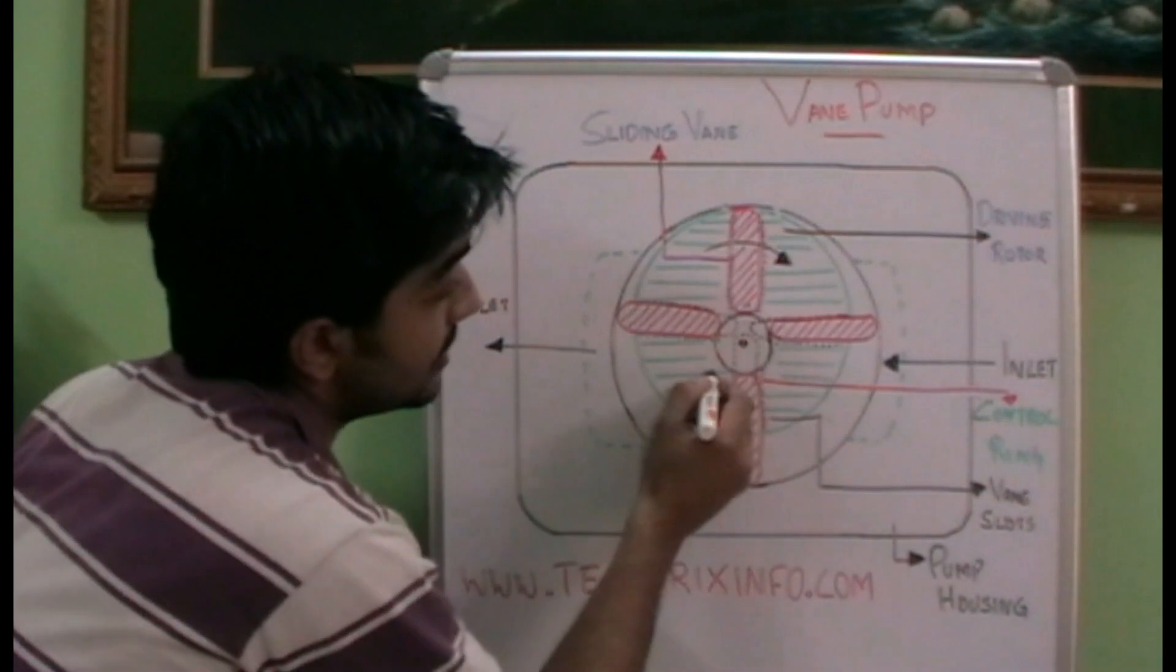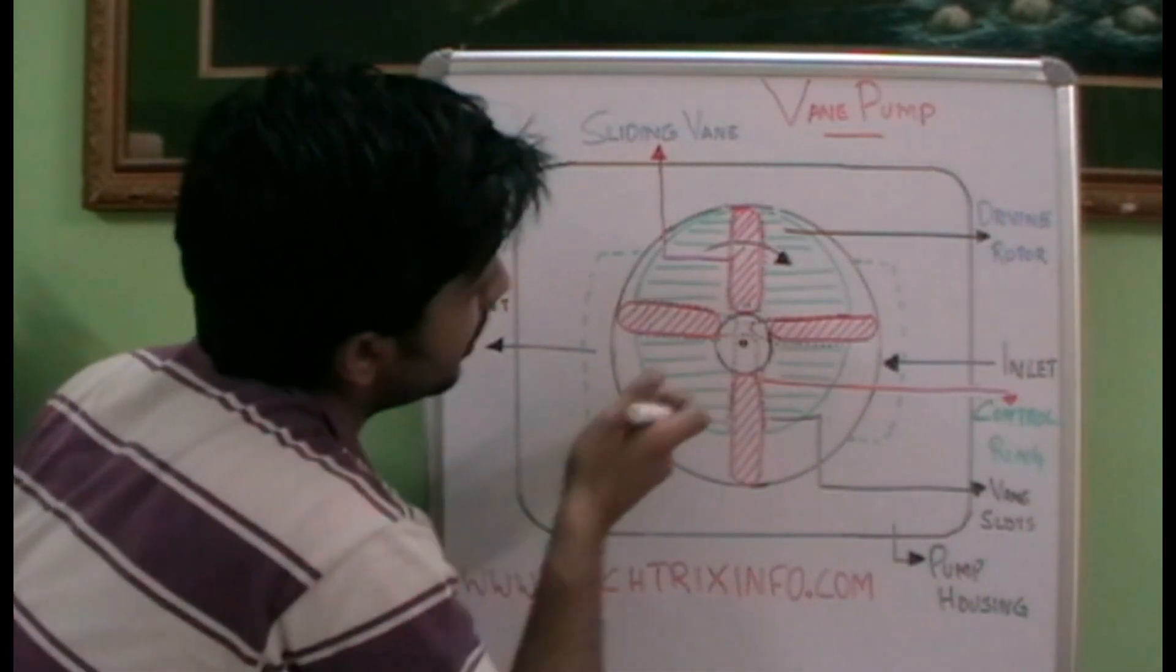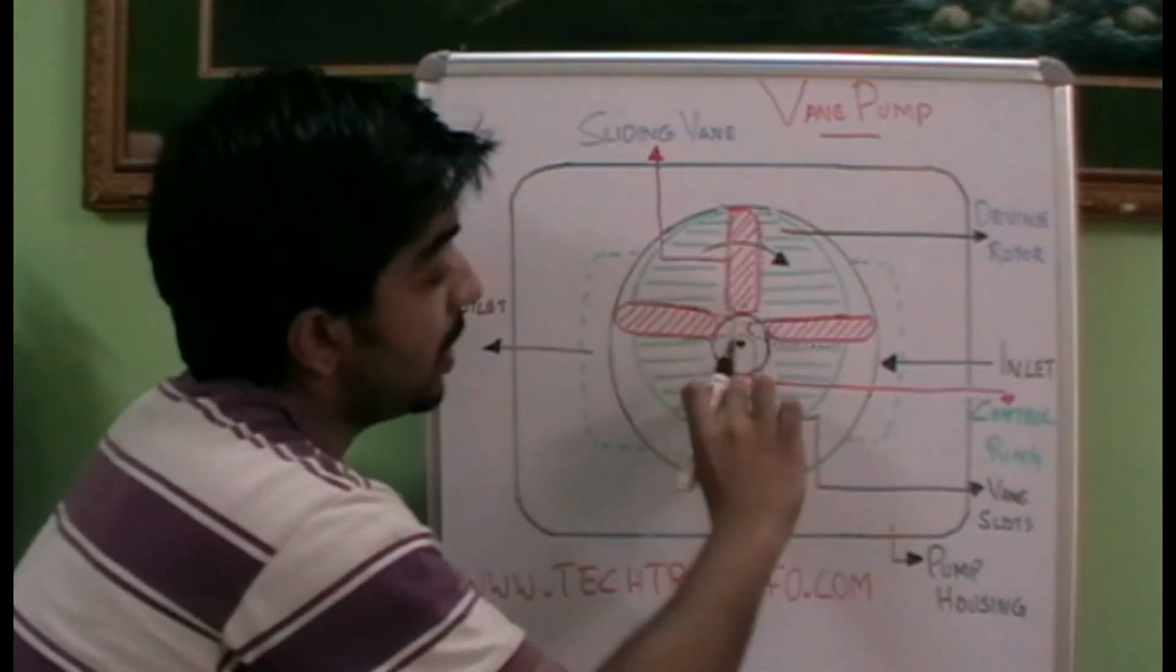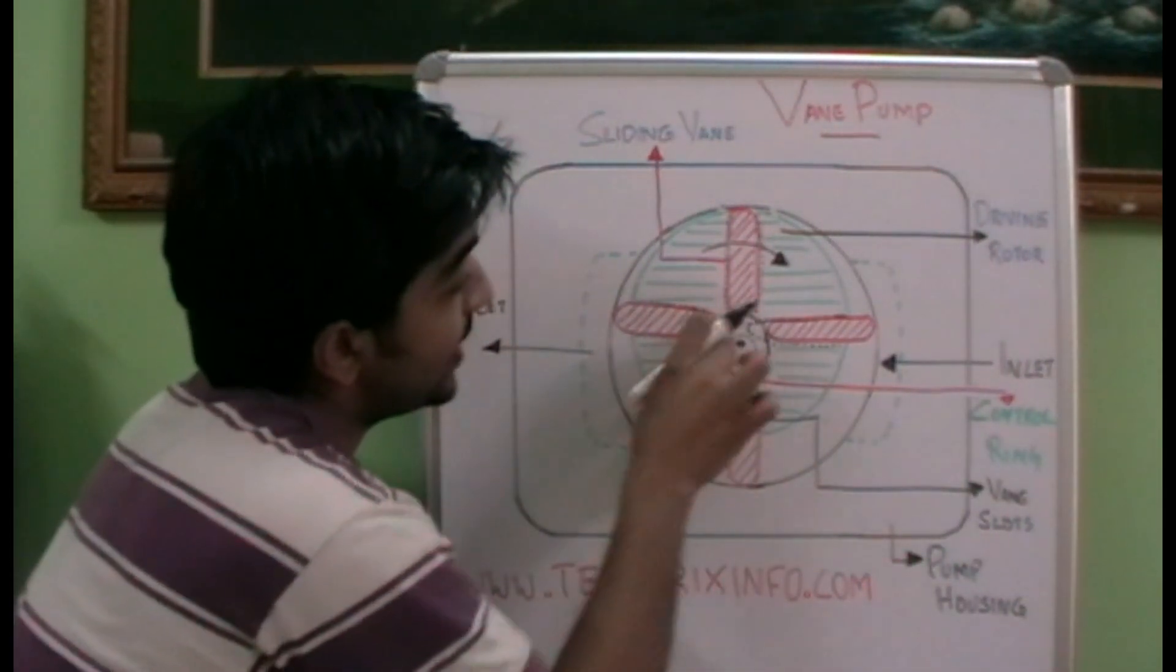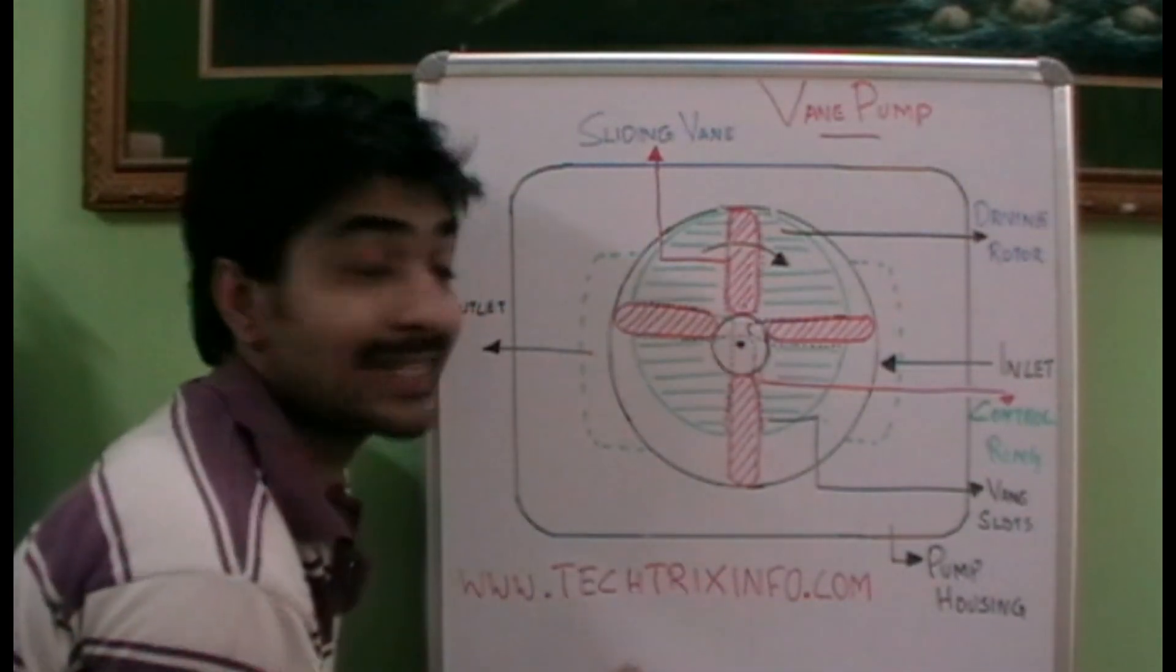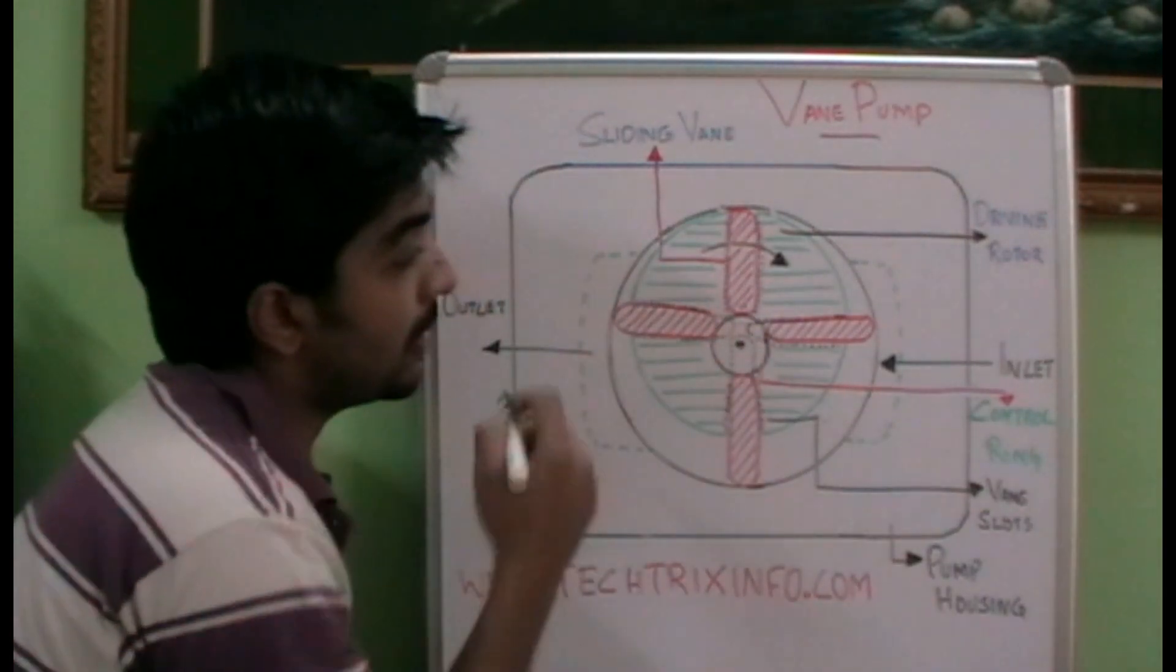When it further rotates you can see these slots will have more area produced over here which will allow these vanes to move inside, and it will be controlled with the help of this control ring which will be always in the center of this vane pump.